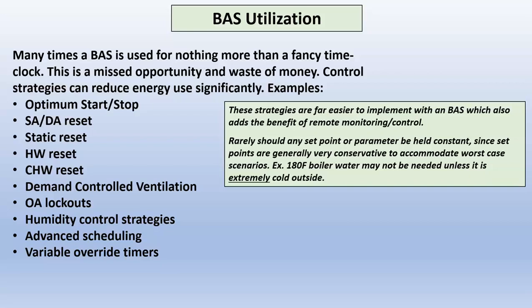So in this case, I actually put resets on the thermostats where they are an override, and they'd go over there and hit it, and it would run the system for so long. I set it at 1 hour, and we have a slide on this a little bit. So, some people set them at 4 hours. I think that's too much. After 1 hour, they can get up, go hit the button again. Saved a ton of money with that, though, instead of running 24/7.